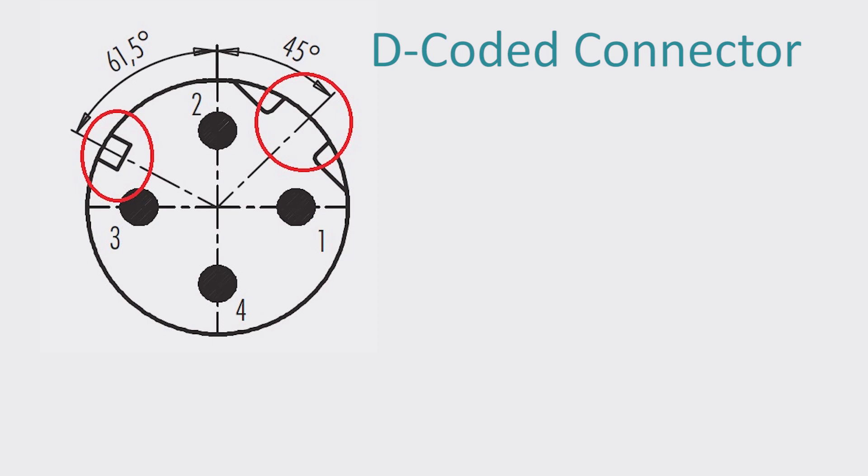The D-coded connector has its own configuration with the distinguishable traits circled in red. This connector type can function on ethernet IP, profinet, and ethercat for up to 100 megabits. The number of pins can vary depending on the network, and it usually falls between 3 to 5 pin connections.